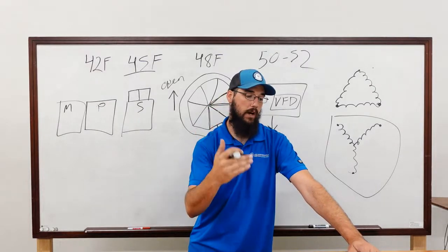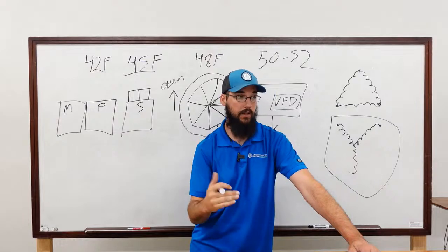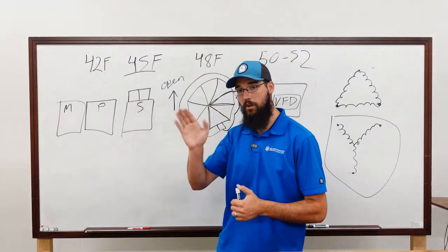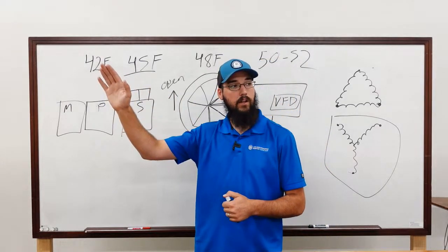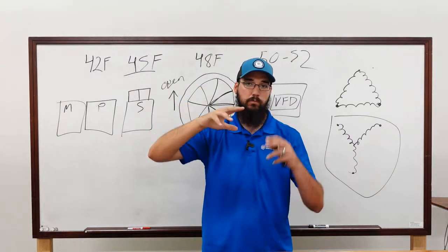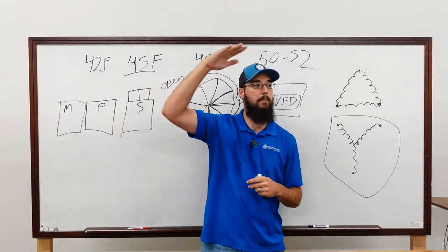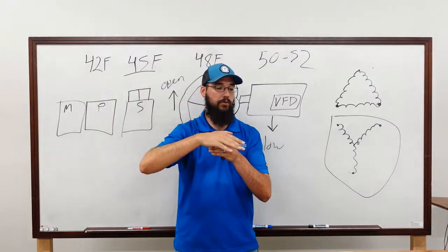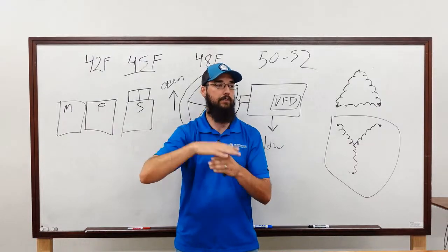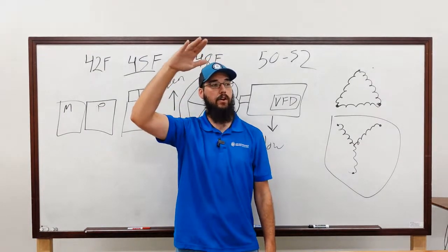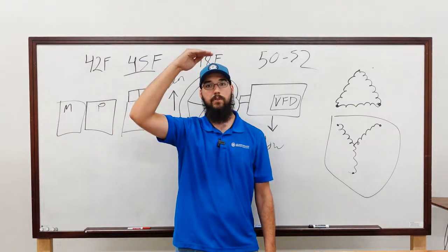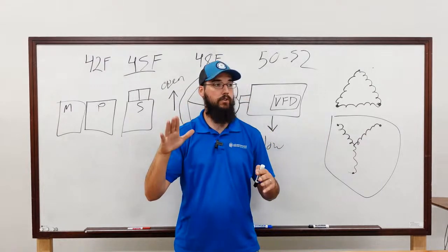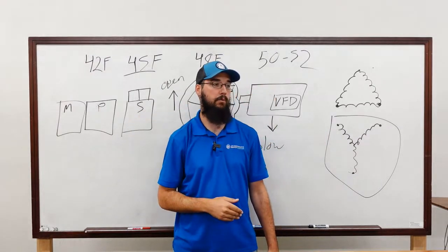So Y delta, solid state, and VFDs use soft starting technology. A solid state just pulses the electronic gates from a low frequency and ramps that drive up, but they're not made to run as a variable system like a VFD is. Once they meet that 60 hertz threshold at the top end and the motor is up to full speed, they lock closed and they're just a straight power path at that point.